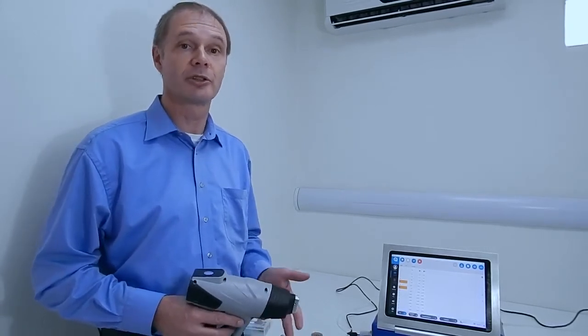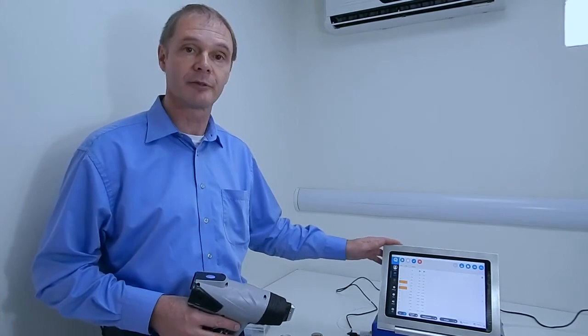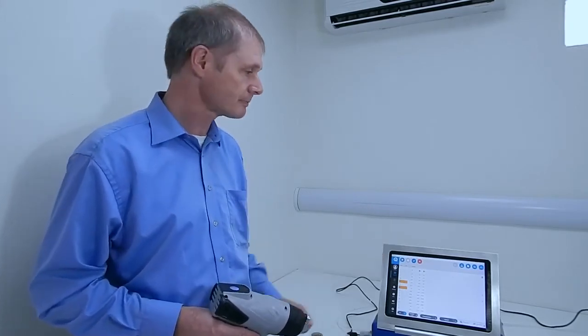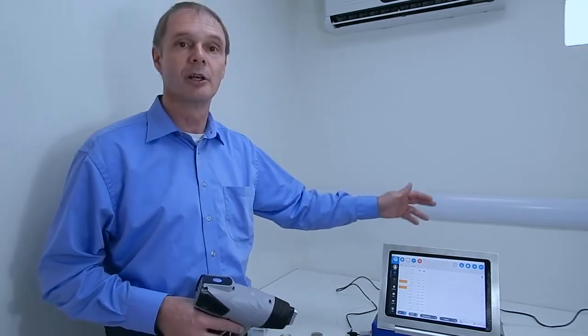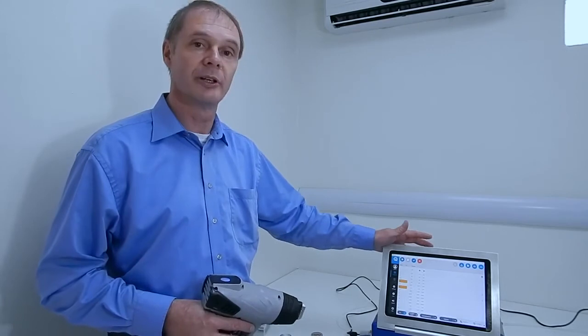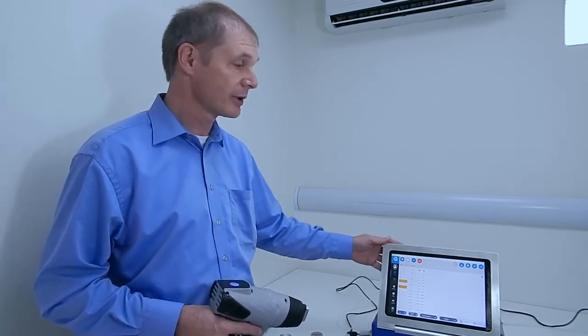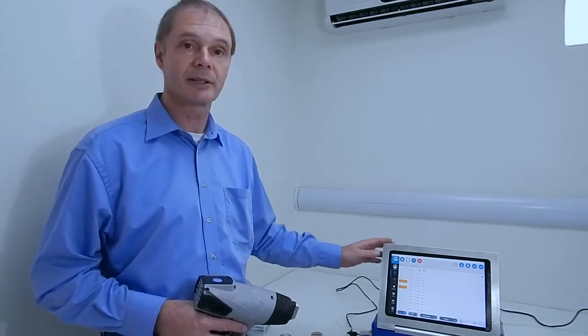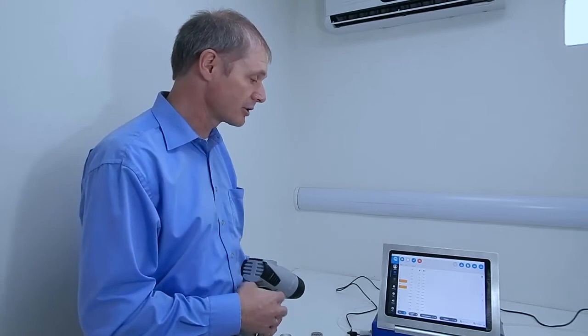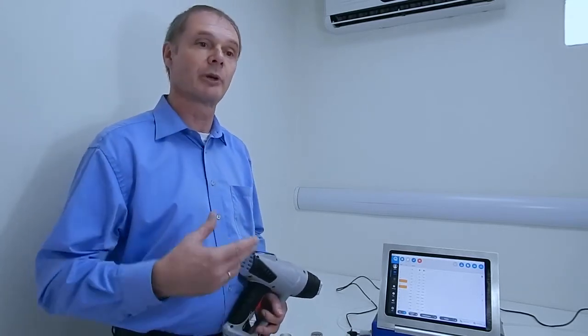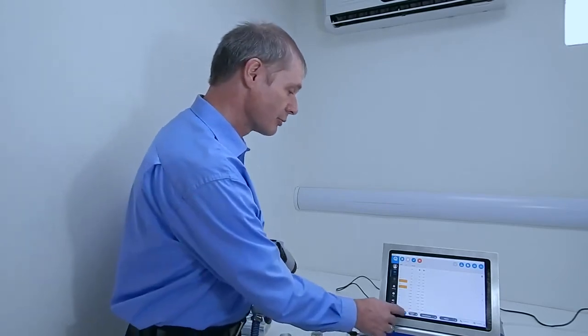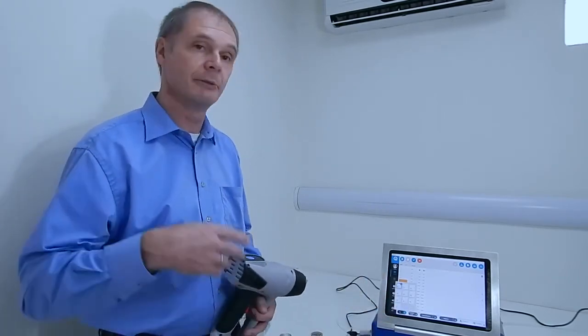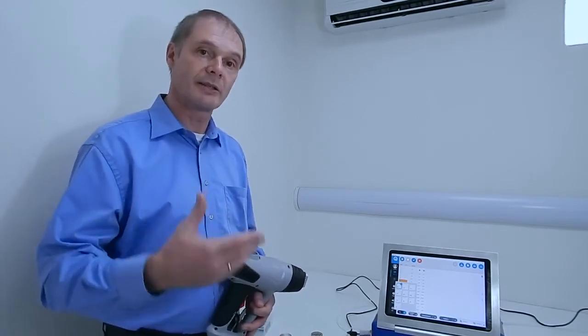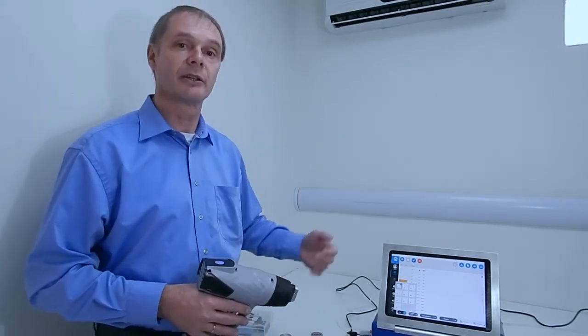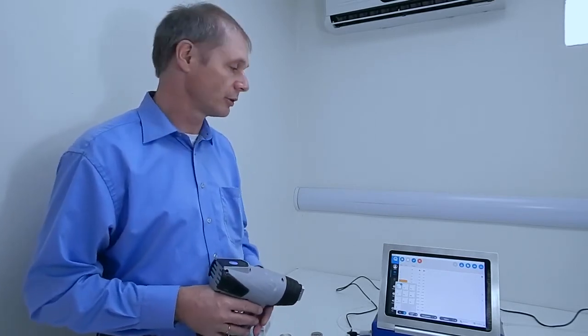At Quantulux we follow a digital strategy, a digital concept, and this means that we have lots of digital services embedded into the instrument. One is the automatic download function. Whenever there is updates available, the system will offer you to download and install the new software, as well as new applications. We provide master calibrations for most metal alloys or metal calibrations, and these can also be updated whenever we have a new version of the master calibration. So if your instrument runs the steel app and we add a new element, we add a new alloy group, we extend the calibration ranges, all these are modifications to the calibration, then the button will become active and you can download and install the new version of your calibration.